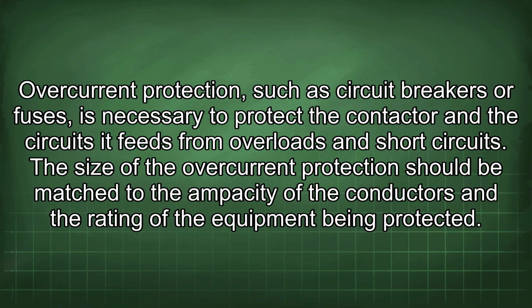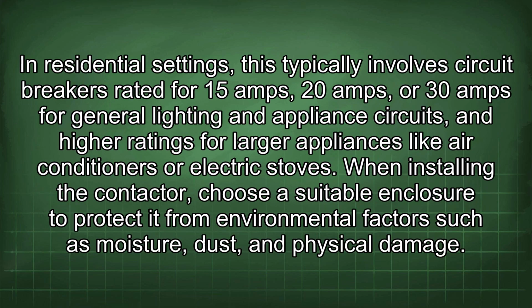Overcurrent protection, such as circuit breakers or fuses, is necessary to protect the contactor and the circuits it feeds from overloads and short circuits. The size of the overcurrent protection should be matched to the ampacity of the conductors and the rating of the equipment being protected. In residential settings, this typically involves circuit breakers rated for 15 amps, 20 amps, or 30 amps for general lighting and appliance circuits, and higher ratings for larger appliances like air conditioners or electric stoves.